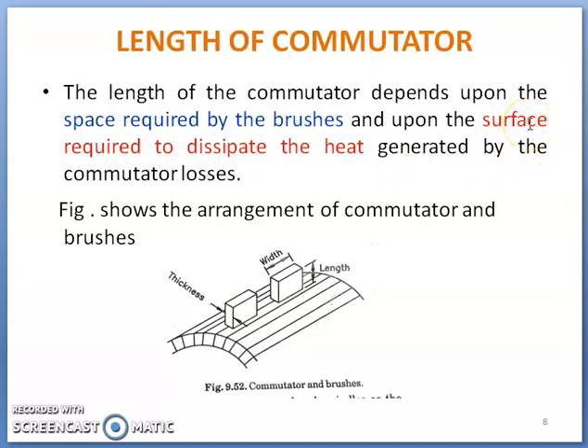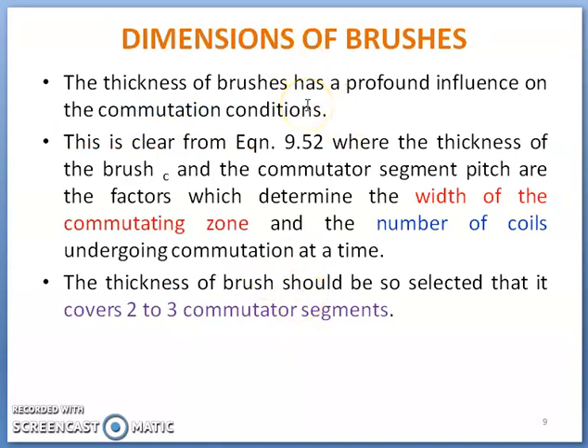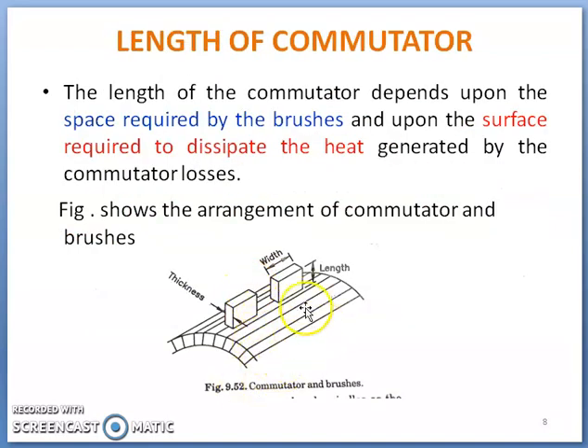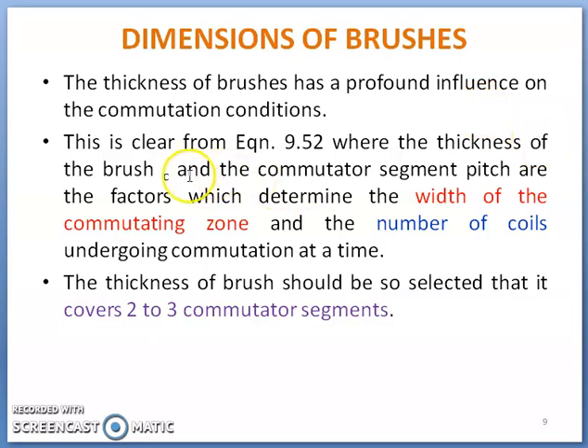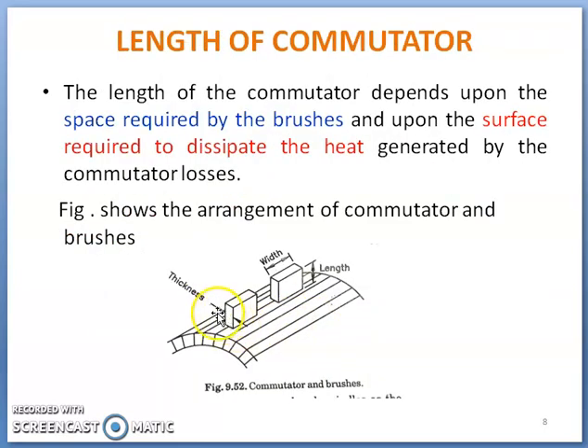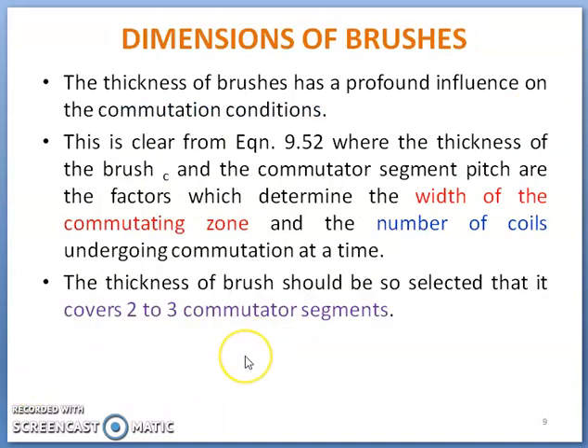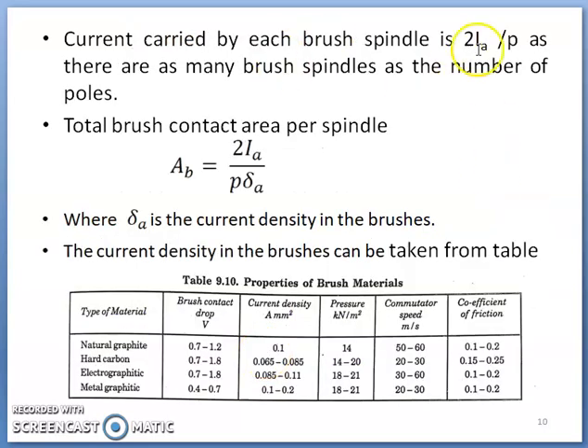Sufficient area is needed to properly dissipate heat from commutator losses during energy conversion. The thickness of the brush has a pronounced influence on commutation conditions. The thickness of the brush and commutator segment pitch determine the width of the commutating zone and the number of coils undergoing commutation at a time. The brush thickness should be selected so that it covers two to three commutator segments on the outer surface of the commutator.